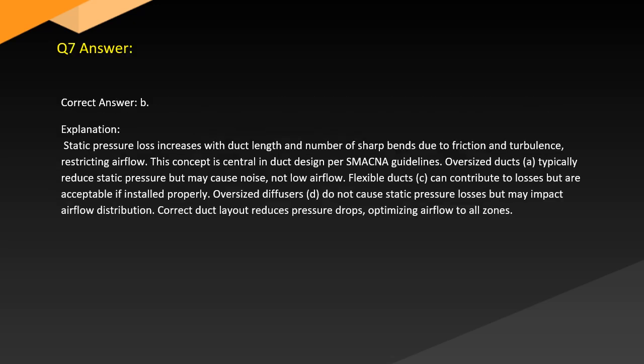Answer. Correct answer, B. Explanation. Static pressure loss increases with duct length and number of sharp bends due to friction and turbulence, restricting airflow. This concept is central in duct design per SMACNA guidelines. Oversized ducts typically reduce static pressure but may cause noise, not low airflow. Flexible ducts, C, can contribute to losses but are acceptable if installed properly. Oversized diffusers, D, do not cause static pressure losses but may impact airflow distribution. Correct duct layout reduces pressure drops, optimizing airflow to all zones.